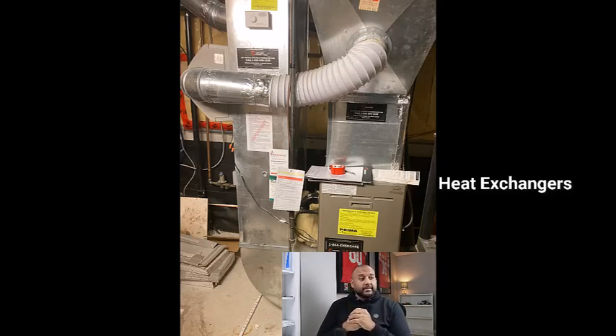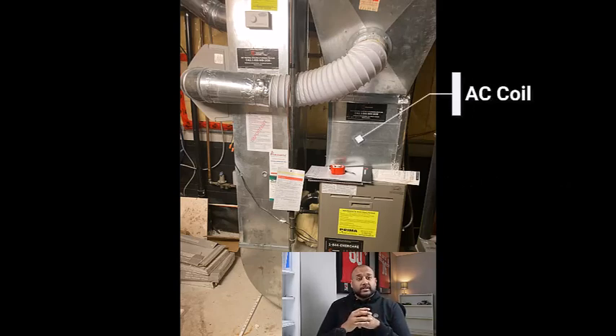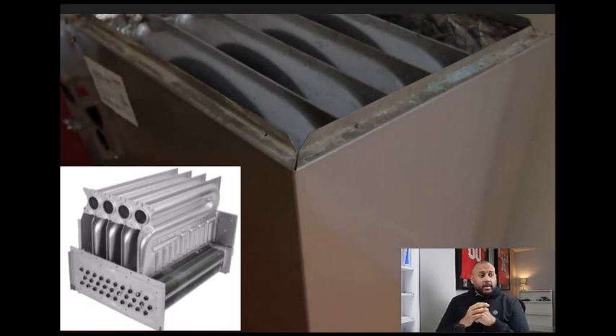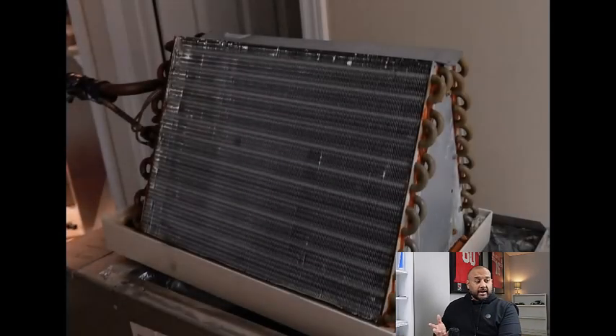Now, with that being said, above the furnace, if you do have an AC unit, what sits inside there is an AC coil. That's where the air passes through it and cools and gets circulated throughout the house. So again, that's probably 19 years old, since that's never been replaced, and that was purchased when we bought the house. So he recommended that we replace that as well. So here's what the top of the furnace looks like. Those 4 panels you see inside there, those are your heat exchangers. It's hard to see right now, but as you look down, the crack could be anywhere along one of those coils. And then here we have the AC coil that sits right above the furnace, up in that ventilation area. I just want to show you what it looks like.